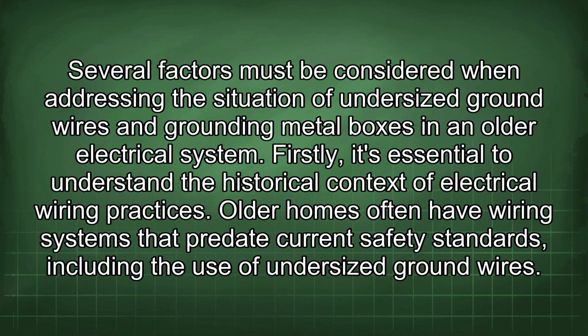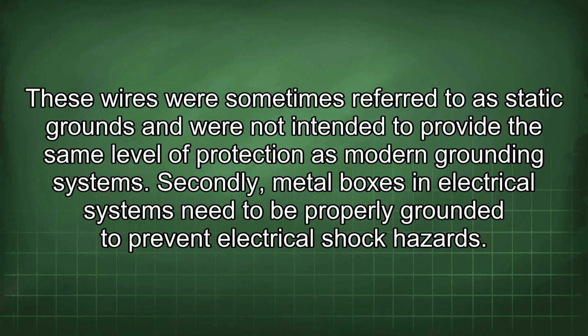Several factors must be considered when addressing the situation of undersized ground wires and grounding metal boxes in an older electrical system. Firstly, it's essential to understand the historical context of electrical wiring practices. Older homes often have wiring systems that predate current safety standards, including the use of undersized ground wires. These wires were sometimes referred to as static grounds and were not intended to provide the same level of protection as modern grounding systems. Secondly, metal boxes in electrical systems need to be properly grounded to prevent electrical shock hazards.